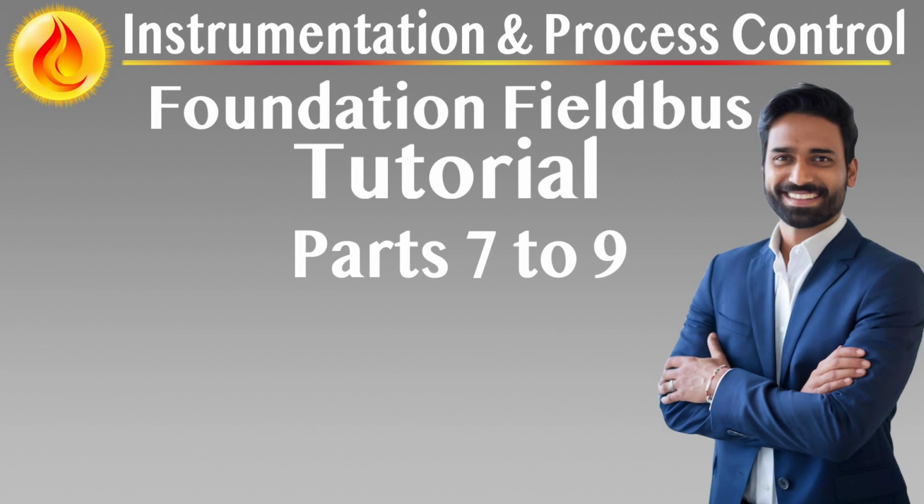Variables such as pressure, temperature, or valve position are maintained within specific function blocks in the VFD and are made available for scheduled communication through virtual communication relationships, VCRs. Another essential function of the VFD is mode management. Each VFD and the individual blocks within it supports operational modes such as auto, manual, out of service, and cascade. These modes control how the block interacts with the rest of the system and allow for safe commissioning, testing, and troubleshooting. For example, setting a block to out of service temporarily suspends its participation in scheduled control cycles while still allowing diagnostics and configuration access.